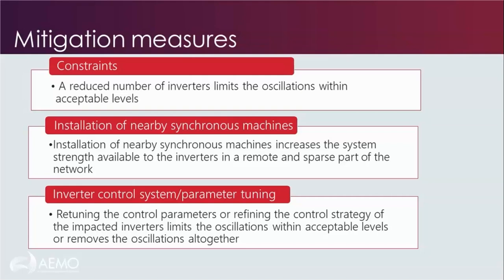The second option considered was installation or utilization of nearby synchronous machines, whether a synchronous condenser or a synchronous generator, if available nearby, which the latter is often not the case. And the third mitigation measure considered was tuning or retuning the inverter control system, or at least the control system parameters. In the next few slides, I'll discuss in more detail the key outcome of each of the mitigation measures that we considered in practice.